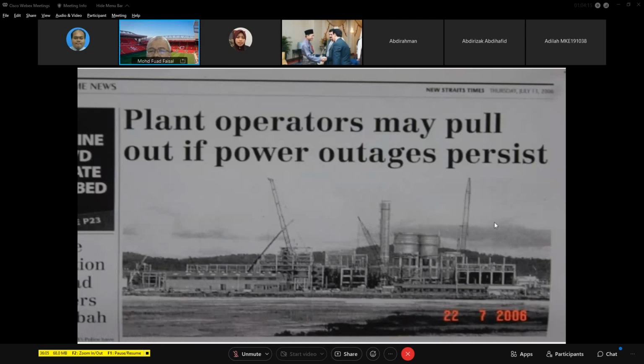Okay, this has happened in Gebeng. As I think we are aware, Gebeng area is an industrial area. So although the newspaper reported outages, it's not true. It's really power quality. So I went there in 2006. Most of the plants there complained about the light blinking and equipment tripping. But to the customer, anything that trips the equipment is called an outage. But as explained just now, an outage is when the voltage goes to zero for more than 60 seconds. But for power quality, it happens for less than 60 seconds. 60 seconds means permanent. So this is not permanent. This is a short duration event.